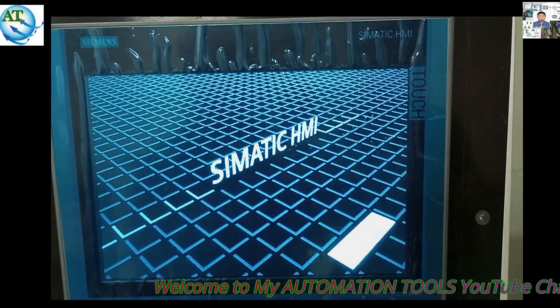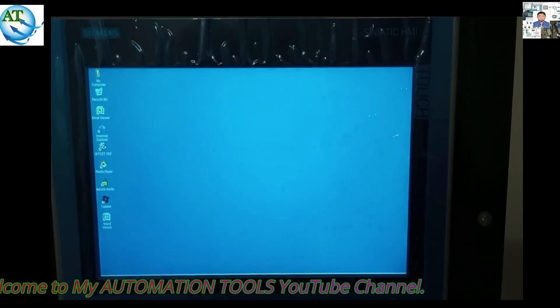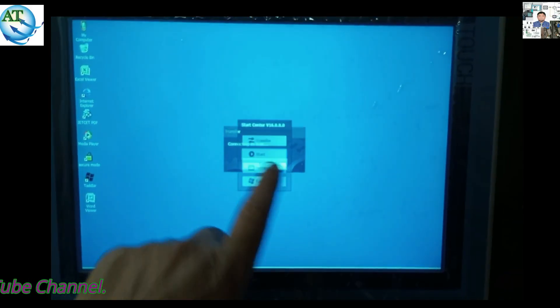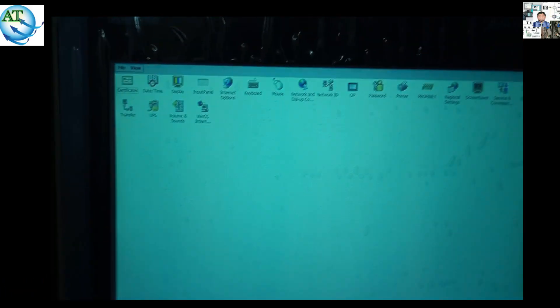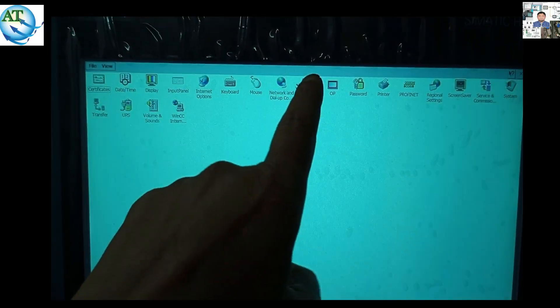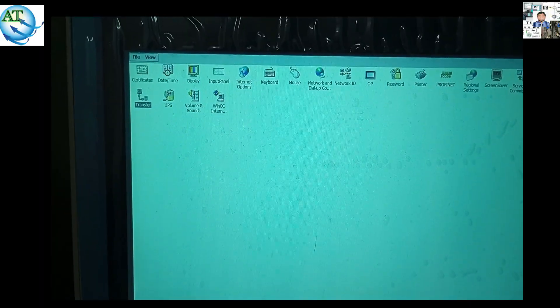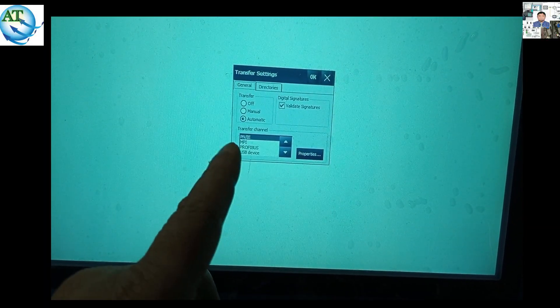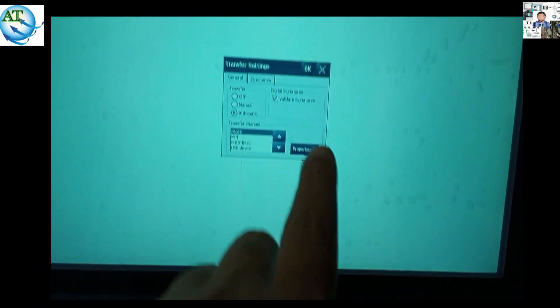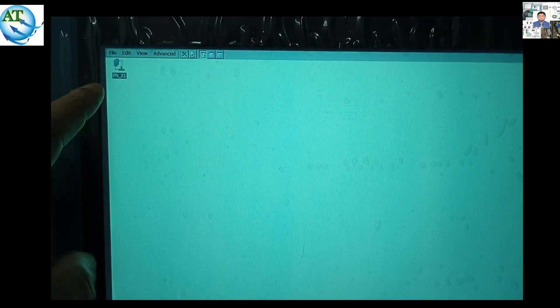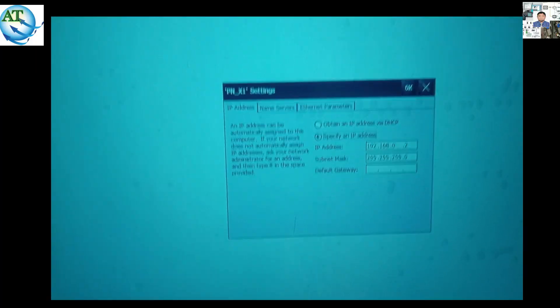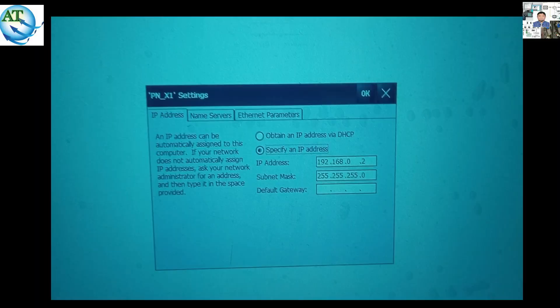After powering up, we go to the control settings and then into the setting mode. From there, we go to the transfer function. We do not select network ID — we go to transfer. In the transfer menu, you can see which option is used to upload or download the program. We select industrial Ethernet, PN interface by industrial Ethernet. We go to properties, and in properties you can see the IP address being used by this HMI. This IP address is 192.168.0.2.